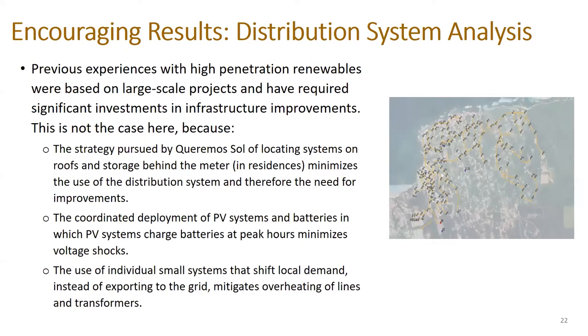As I said before, my previous experience with doing a high penetration, particularly in island systems, where you will only have a modest amount of fossil fuel generation, and you're coming in and putting in a relatively large solar penetration, you get all kinds of issues associated with that. And one of the primary ones is you're moving a lot of power on the distribution system that it really wasn't necessarily designed to do. Using the strategy that was pursued here, that is putting the resources where the load is, we minimize the amount of power that actually has to move on the distribution system.